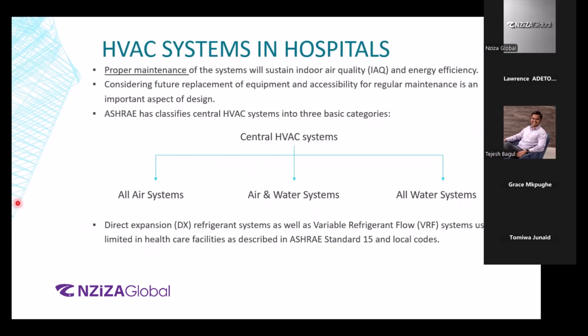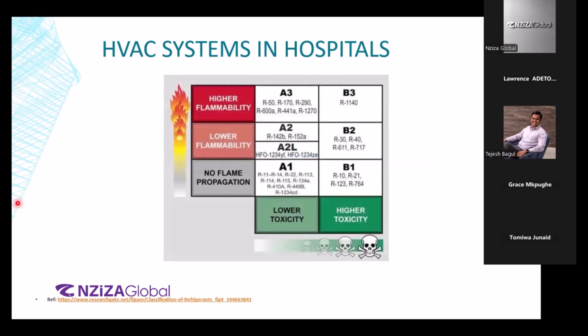On the next slide, I'll tell you why. But the DX system, VRF system, you must have heard about VRF, right? Variable refrigerant flow. I think Daikin calls it variable refrigerant volume, VRV. The reason why these are not preferred in hospitals is because they are limited by the ASHRAE 15 standard as well as the local codes. Okay. This is the reason why it is limited. Okay. The most commonly used refrigerant, right? So every HVAC system will have a refrigerant flowing through it, right? The most commonly used these days is R410A, right? We have 410A somewhere.